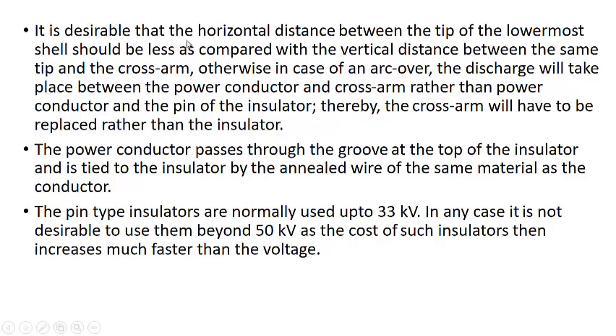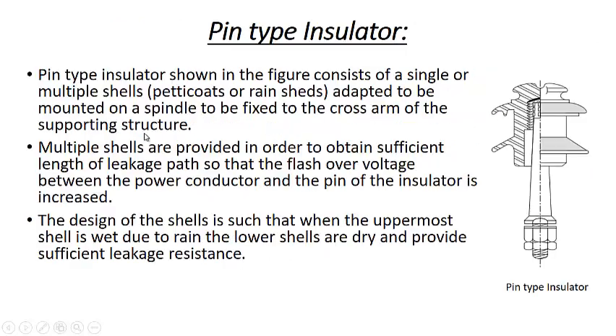It is desirable that the horizontal distance from the tip of the lowermost shell should be less than the vertical distance between the same tip and the cross arm. Otherwise, the discharge will take place between the power conductor and the cross arm rather than between the power conductor and the pin of the insulator. Thereby, the cross arm will have to be replaced rather than the insulator.